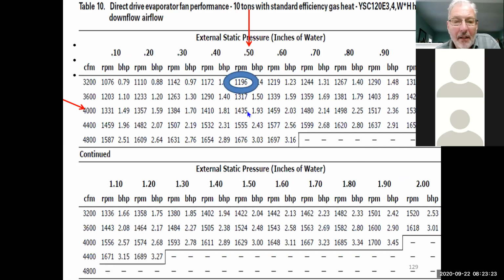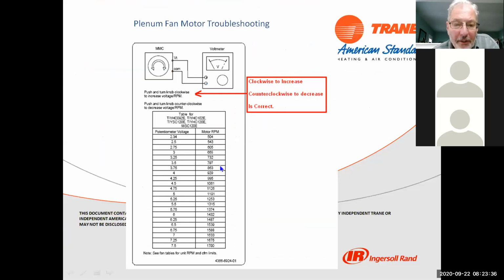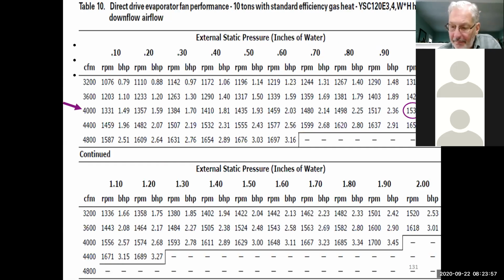So the unit comes set at 1196, our target is 1435. So if you look at this chart, I'm going to back up here. If you look at this chart, 1435, well, 1432 is as close as I can get, is 6 volts DC. Again, if we left it at 5, we'd be at 1191. So what we want to do is change that to 6 volts DC and get to 1432 RPM. And that's our target in that particular case.